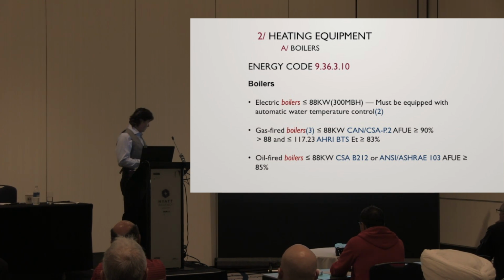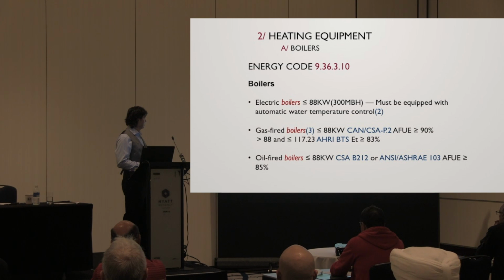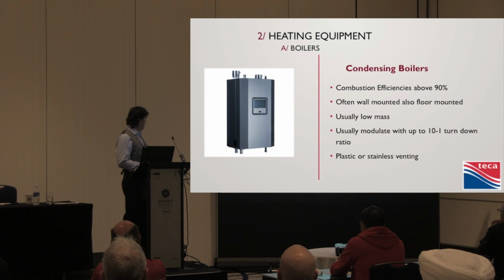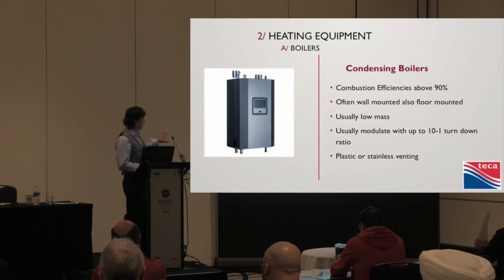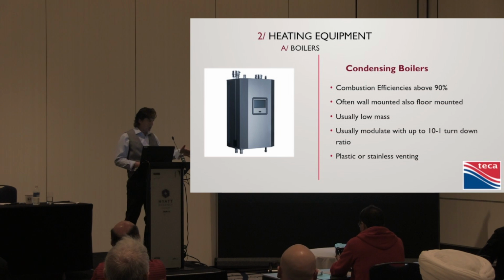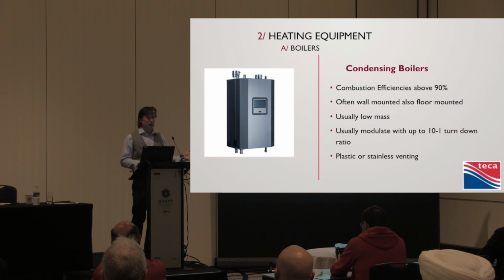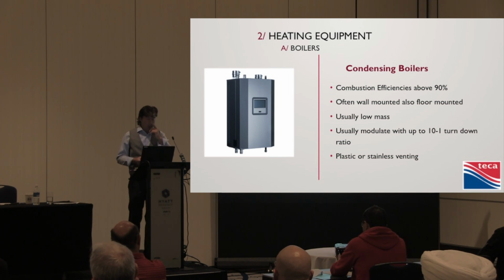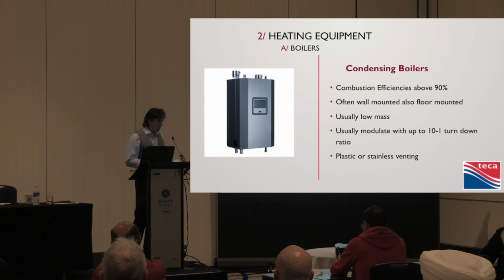Oil-fired boilers, we don't see a lot of those, but on Vancouver Island, etc. What can you do there? It's 85%, non-condensing. Your classic condensing boiler, I don't know if that's Triangle Tube or who that is, combustion efficiency is above 90%. Most of these are wall-mounted boilers. There are condensing boilers that are floor-mounted, and certainly there are commercial, large floor-mounted condensing boilers, all varieties of condensing boilers.